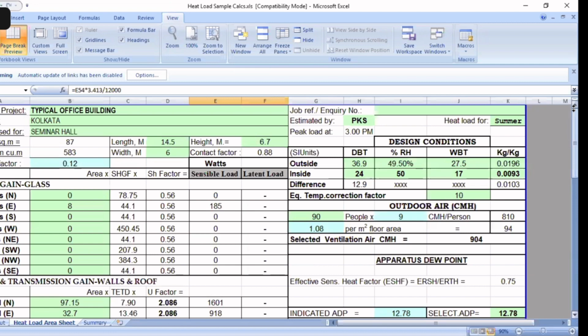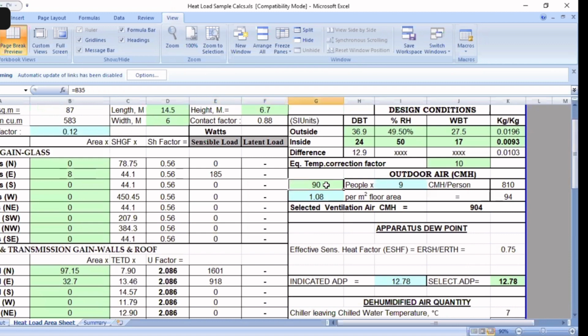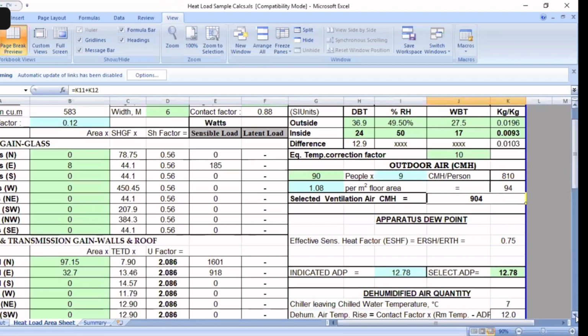And similarly, here the number is 90 people, at 9 CMH per person, so 810 CMH, and 1.08 CMH per meter square. The area was 87 meters square, multiplied by 1.08, which gives me an additional 94. So the total is 904 CMH total air quantity, which has been considered in the calculation for latent heat and sensible heat.